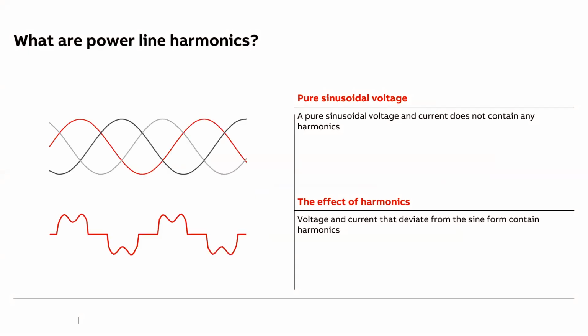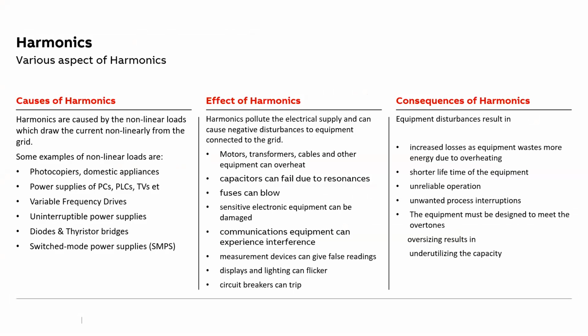Normally, if we have the signal available, the power is a pure sinusoidal sine wave at 50 hertz. However, because of harmonics, this sinusoidal waveform gets disturbed, and we get a distorted waveform. So that is the issue with harmonics. Now, what causes harmonics?